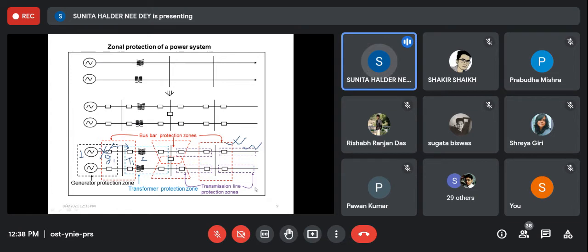But if you do not allow that high transient current to that power system, the solar power generating station, then you should disconnect within 10 millisecond. Otherwise you may wait up to 20 millisecond. So the relay is sensing every time the current is high. When it is peak, it will sense, but it will take time to operate up to 20 millisecond. So within 20 millisecond, that transient will die down. It will not operate. But if you want to set that within 10, whenever there is a transient, even at say 5 millisecond, it should operate. Then we should set the relay in that way. So it will depend on how critical the system we are protecting. Have you understood?